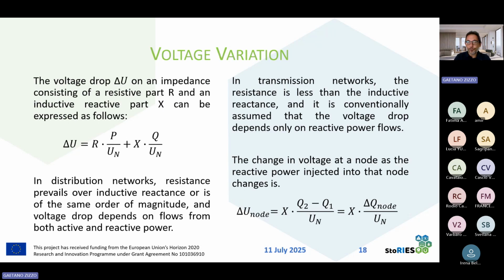We know that the voltage drop or the voltage increase in case of distributed generation on an impedance consists of a part depending on the active power and on the resistance of the line, and on a part depending on the inductive reactance of the line and on the reactive power. And so we can use this expression on the left for calculating the voltage drop or the voltage increase in a line. In distribution networks, we have resistance and reactance that are in the same order in case of medium voltage line, or we have resistance that prevails over inductive reactance in low voltage lines. While in transmission networks, usually the resistance of a line is negligible with respect to the reactance.